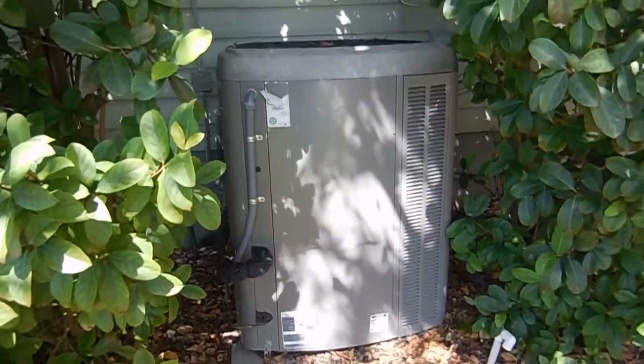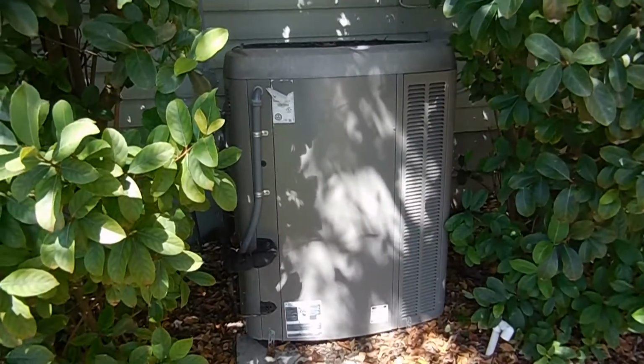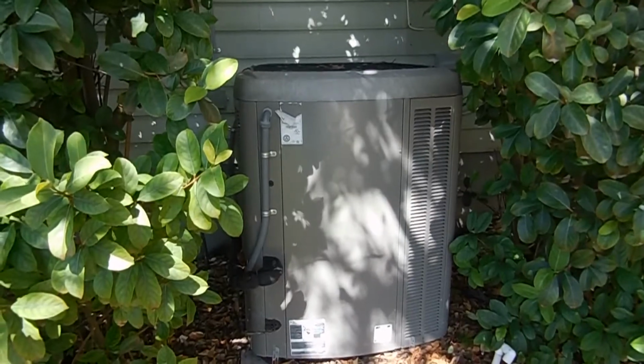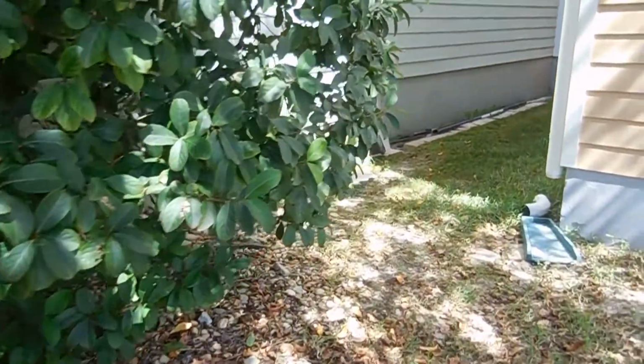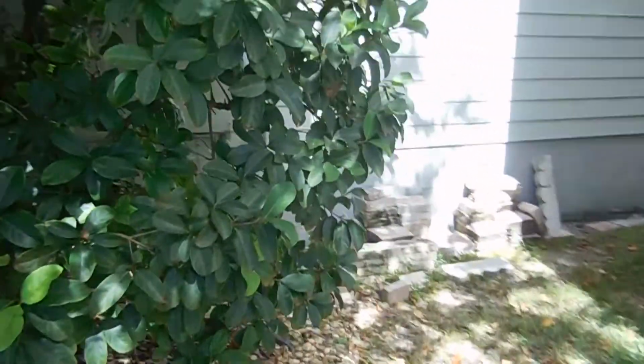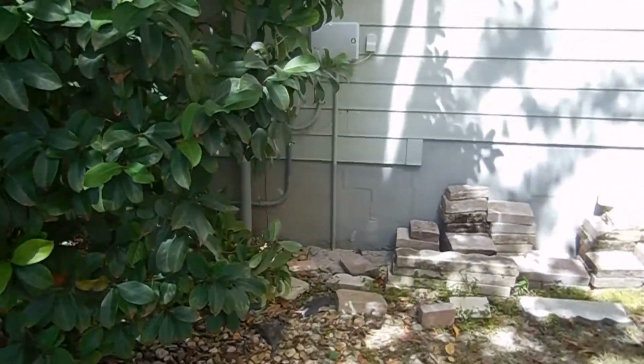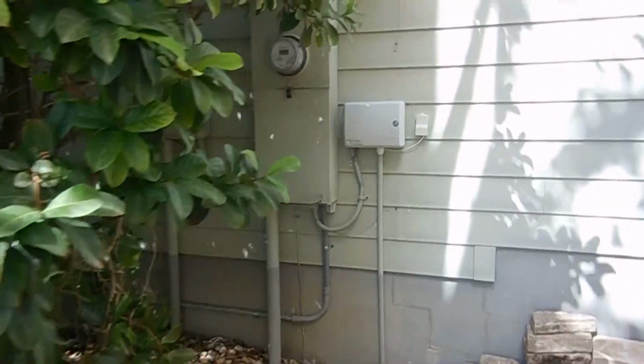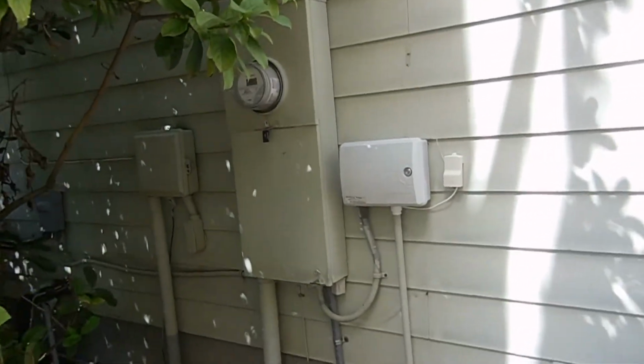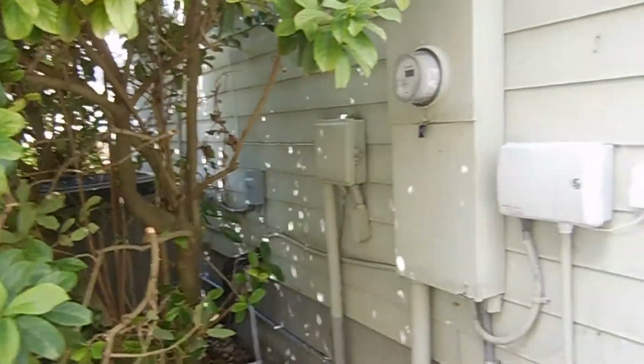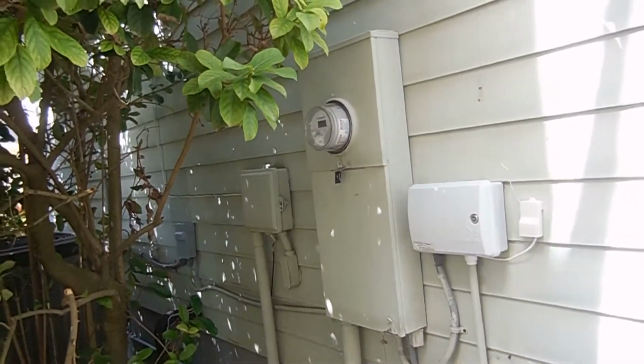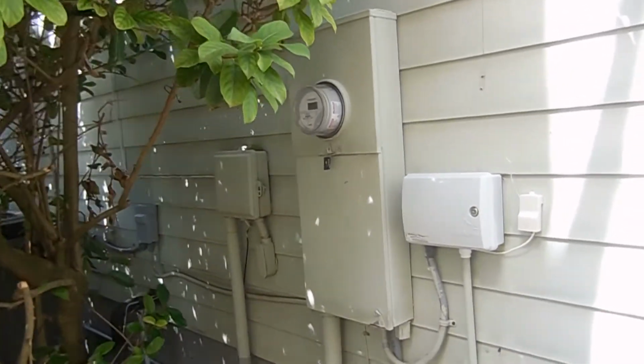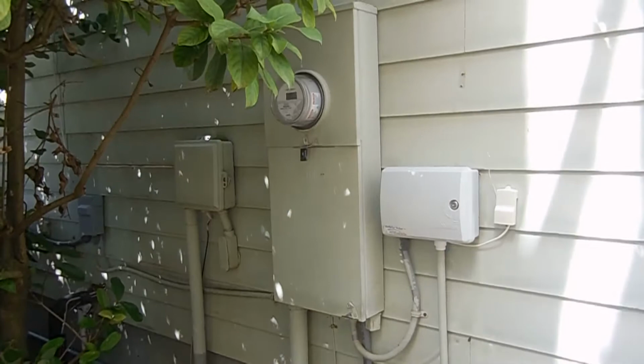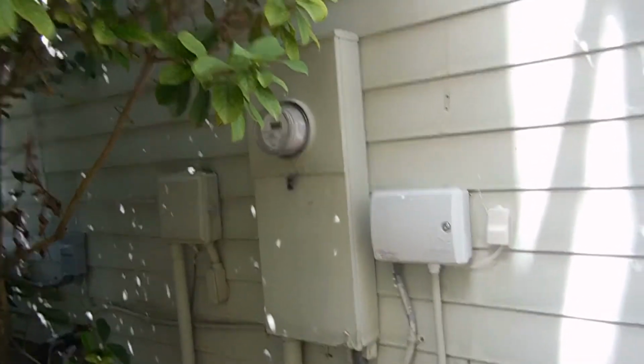The only thing I found as a question mark with this particular unit is it's 5-ton, and 5-ton units are typically installed in homes that are 2,700 to 3,000 square feet. This house is only 2,000 square feet and a little bit of change, so I'm not sure why they went with a 5-ton. You'd have to check with the contractor that installed it. Typically the most common problem with an oversized unit is it might cool the house too quickly without necessarily pulling humidity out.